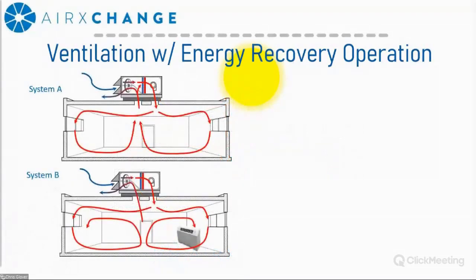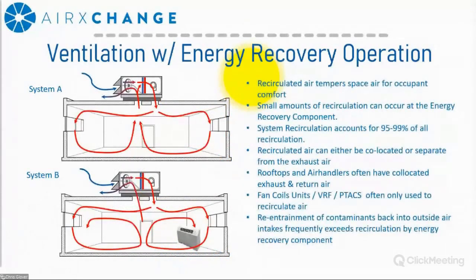All right, now I wanted this slide. It's important to recognize the difference between the sources of recirculated air inside the space. If the HVAC system just pumped outside air in and exhausted it immediately, it would be exceedingly costly to condition that air. So what a typical HVAC system does is it recirculates a portion of that air to temper it, so you can maintain occupant comfort. So the system recirculation accounts for, in most systems, 95 to 99% of all the recirculated air within the space. Now, recirculated air can either be co-located or separate from the exhaust air stream.